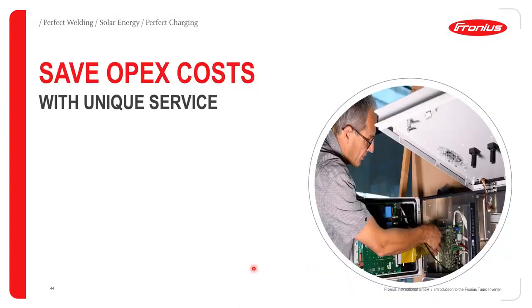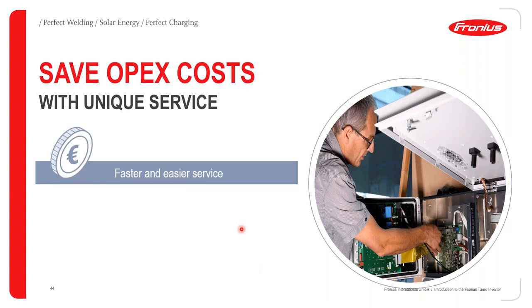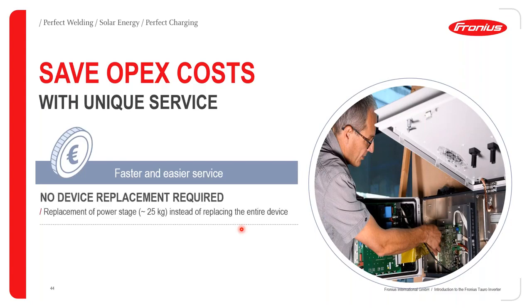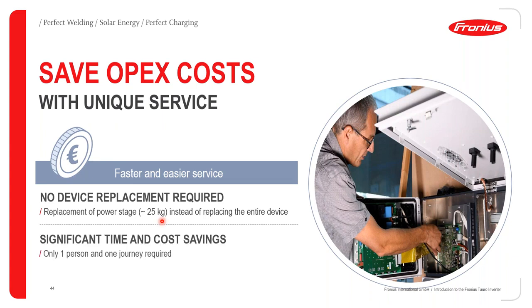Good. So in terms of OPEX, the reduction of OPEX costs, this we achieve via a unique service process. This means that in case of any issue, any anomaly, the entire device does not have to be replaced. This is made possible because of the modularized nature of the Tauro, meaning that, like I said earlier, the entire device does not need to be replaced. Take an example of the power stage, which weighs about 25 kilograms. So instead of replacing the entire device, the power stage can simply be replaced on site by just 1 person, which of course saves significant time and cost, because just 1 person needs to do this replacement. So an entire team of engineers or technicians doesn't have to go to site, which is a very, very big plus when it comes to OPEX cost saving.